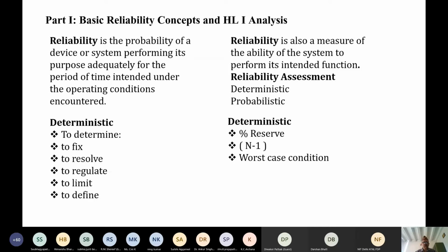Another is to fulfill the n-1 criterion. That means if one of the generating units fails, the system should continue to supply the demand imposed on the system. One unit may be any unit, but the worst impact on the system will be if the largest unit fails. So sometimes it is also called loss of largest unit, LOLU. If a system has a very large unit and that unit fails during peak load condition, then there might be a scarcity or deficit of power. So the n-1 criterion should be fulfilled, or that can be one of the deterministic criteria in the power system. And another is a worst case condition.